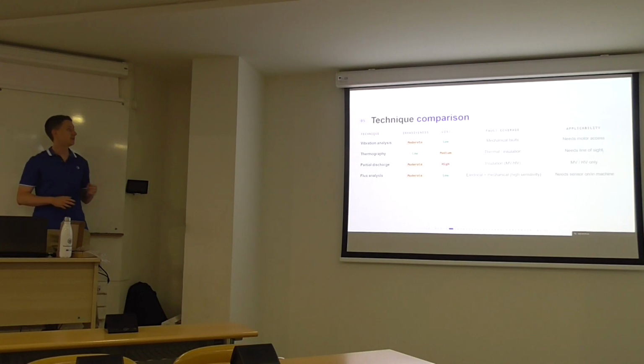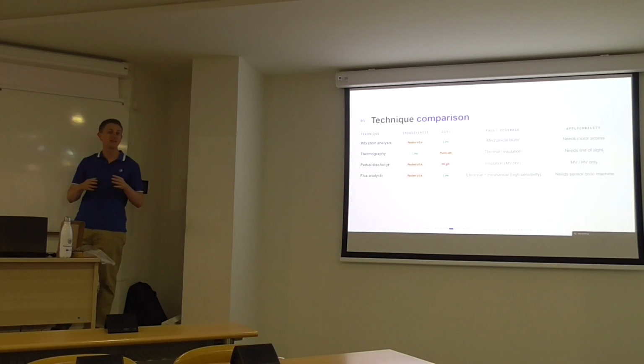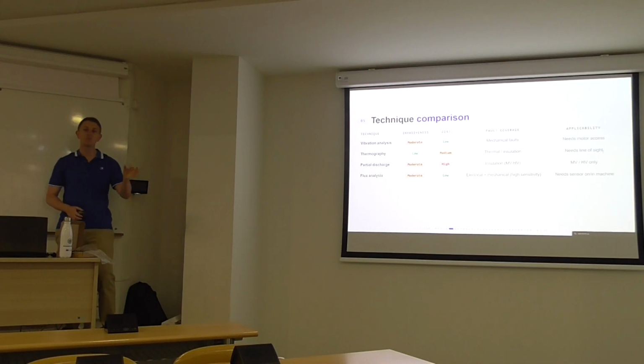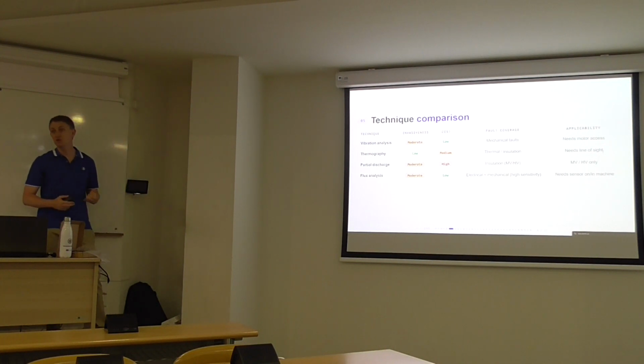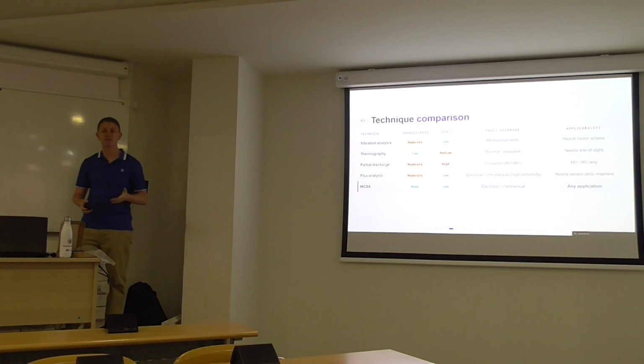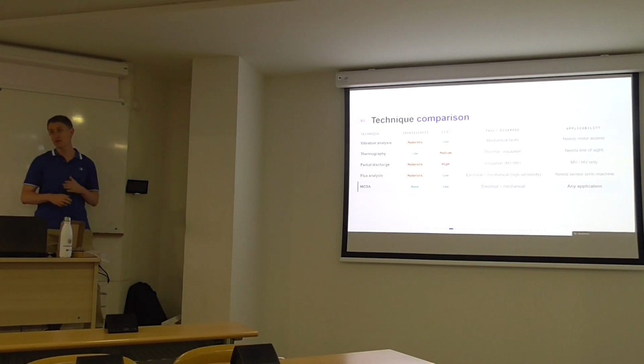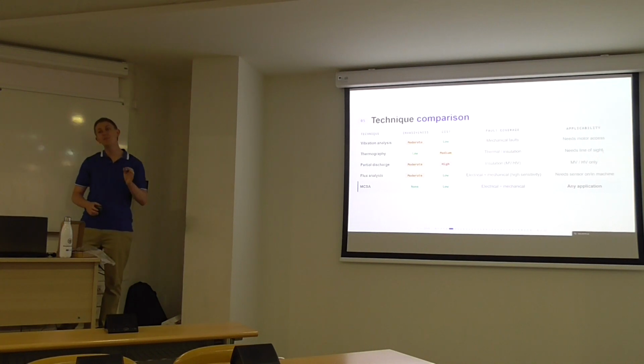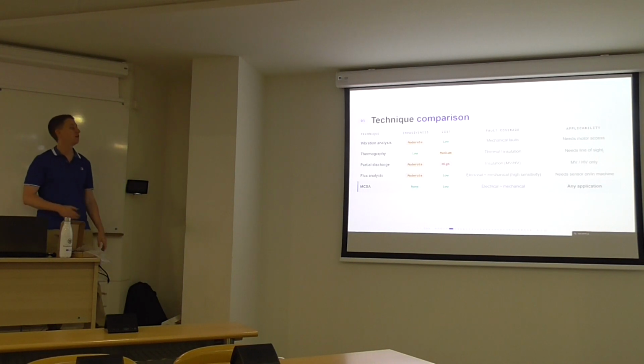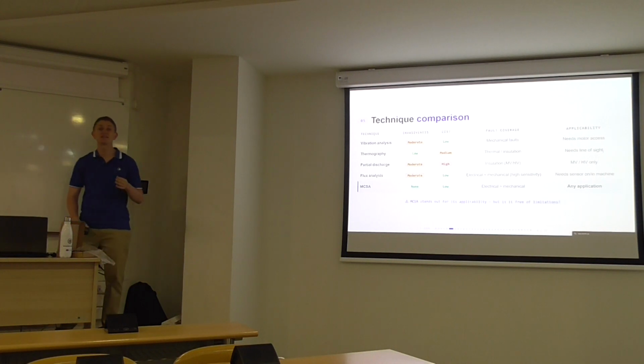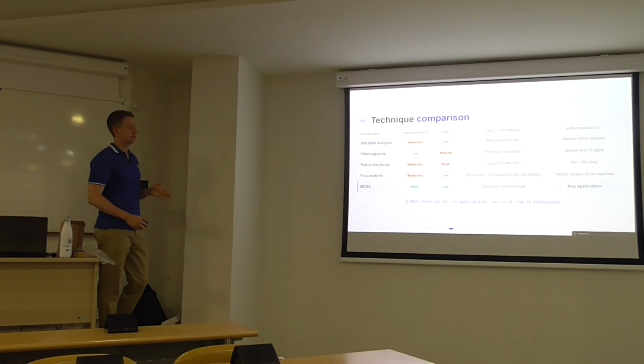And then in flux analysis, once again, the invasiveness is moderate. We need to reach the motor to place the sensor in the housing or inside the motor. The cost is low. At the end of the day, it's just a coil. And the fault coverage is electrical and mechanical with high sensitivity. And finally, we have MCSA, where the invasiveness is absolutely not invasive. The cost can be very low if you custom design your sensors, and the fault coverage is electrical and mechanical. So MCSA stands out for its applicability.